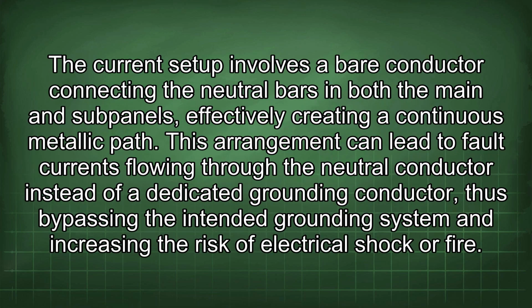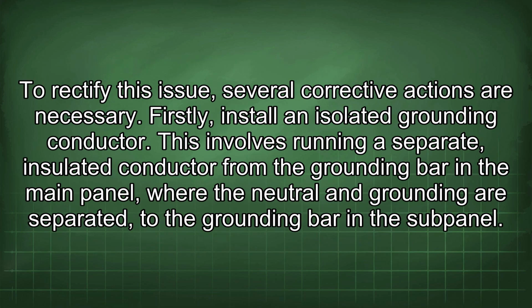The current setup involves a bare conductor connecting the neutral bars in both the main and subpanels, effectively creating a continuous metallic path. This arrangement can lead to fault currents flowing through the neutral conductor instead of a dedicated grounding conductor, thus bypassing the intended grounding system and increasing the risk of electrical shock or fire. To rectify this issue, several corrective actions are necessary.